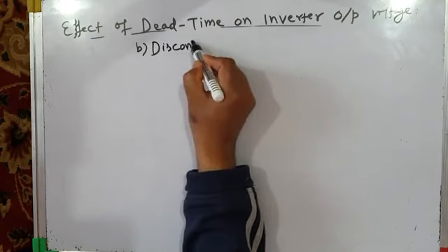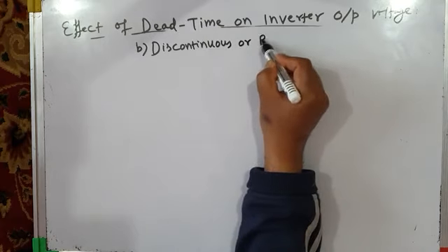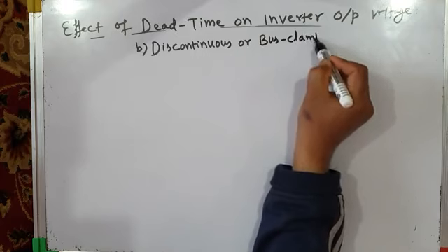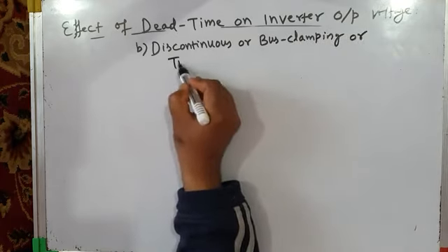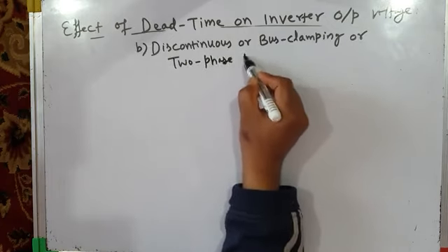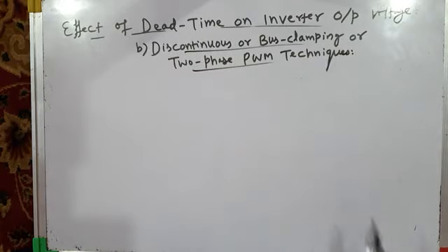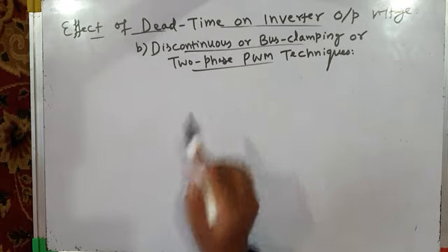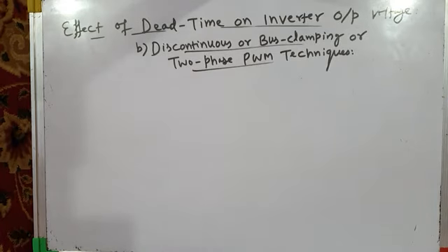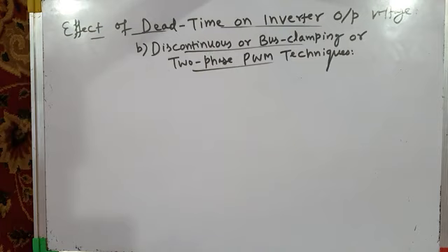These are called Discontinuous or Bus Clamping PWM techniques, also known as Two-Phase PWM techniques. They are called Two-Phase PWM techniques because one of the phase legs is clamped to either the positive DC bus or negative DC bus, and at any given instant, two phases will be switching while one phase will be clamped to the DC bus.